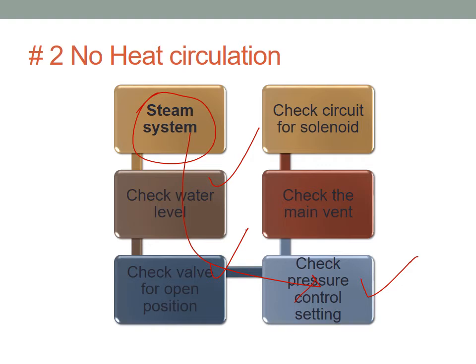Check the main vent. If the vent for the system is not functioning and there is no way for the air to come out of the system, it's not going to push steam. Steam is lighter than air in density, especially the steam that we make. So if there is no way for the air to leave, the steam is not going to displace the air. It will only compress it, and that doesn't help us.